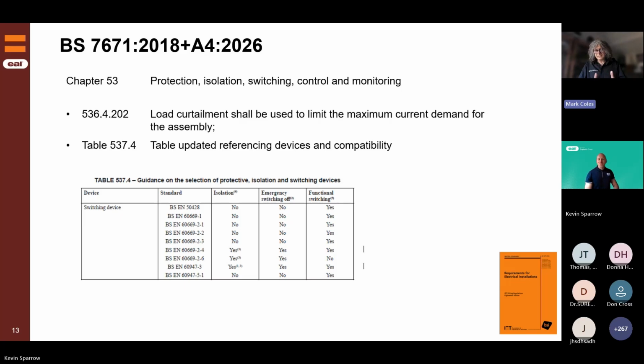Now, what's in IET guidance is a kind of keep-you-out-of-jail approach. It won't give you the most economical result, but it will err on the side of caution. But with engineering experience and your judgment and knowing how the installation will be used, it allows you to make a better assessment of maximum demand. And what this is saying in 536.4.202 is that load curtailment can be used.